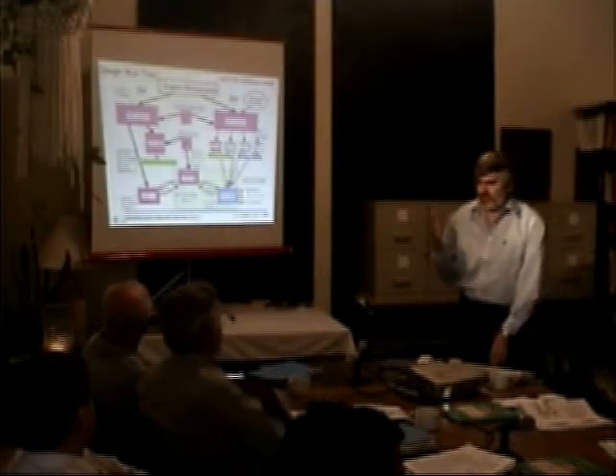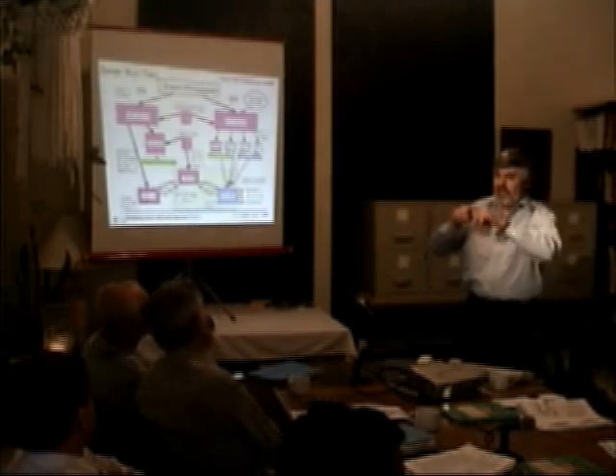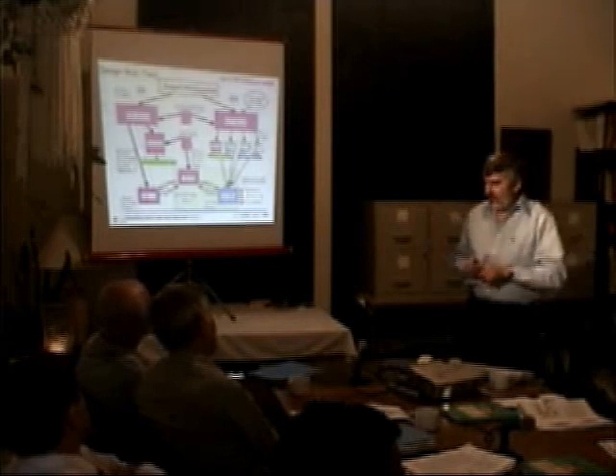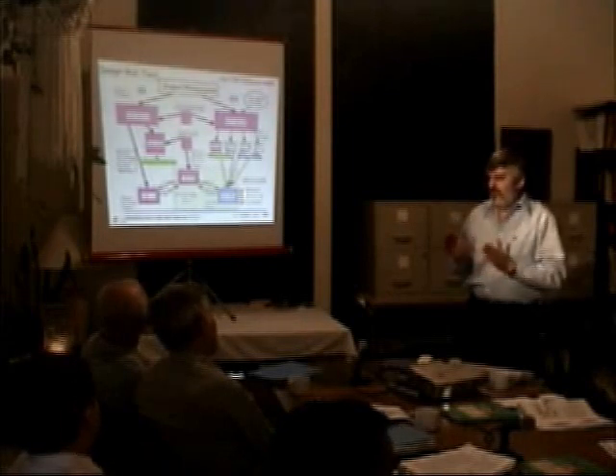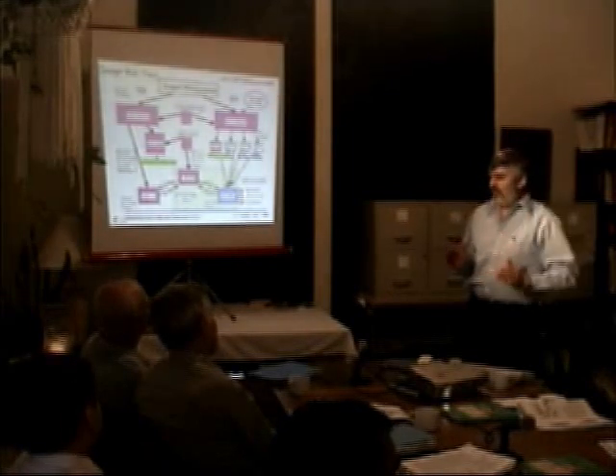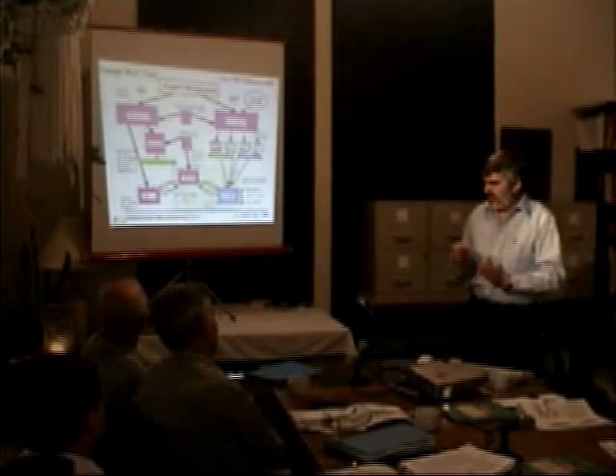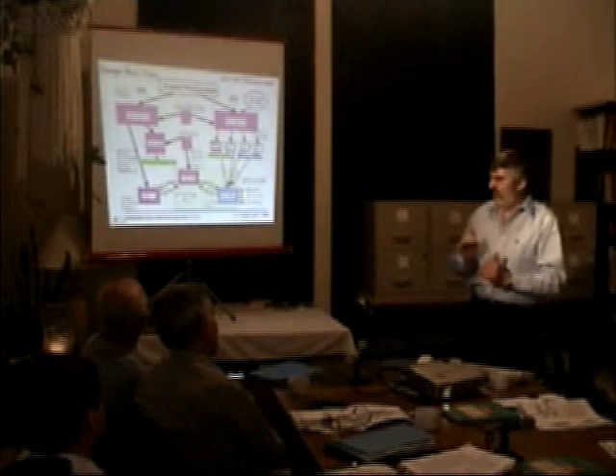The real-time algorithm is that sequence of operation that is identifying the photons. Adding the surrounding element for each processor. Summing the one to the right, summing the one to the left, making a subtraction, and finding the centroid for the X, then the centroid for the Y. So all this is the algorithm.